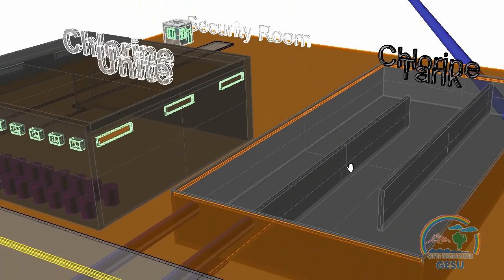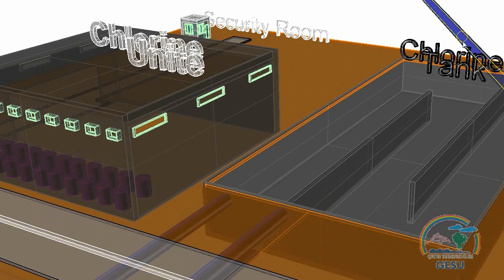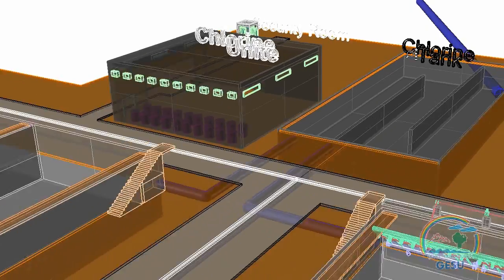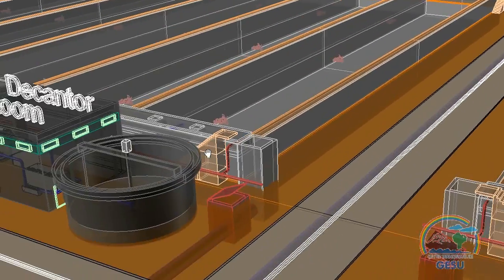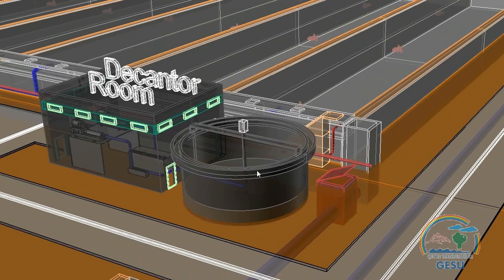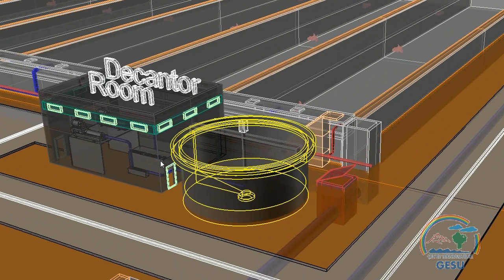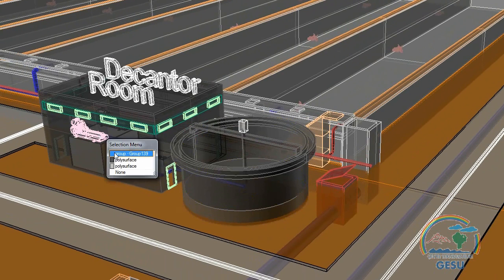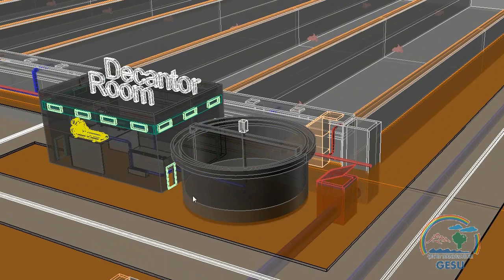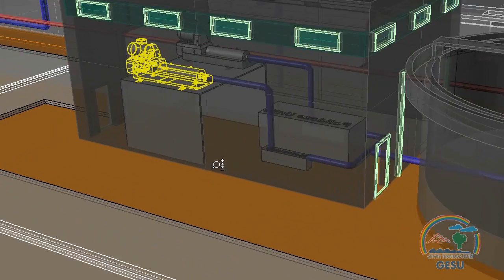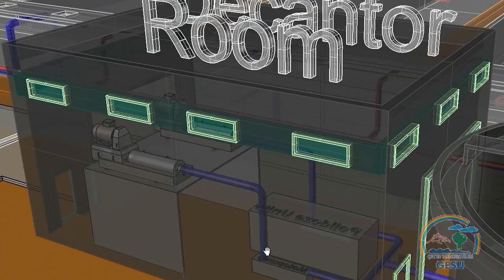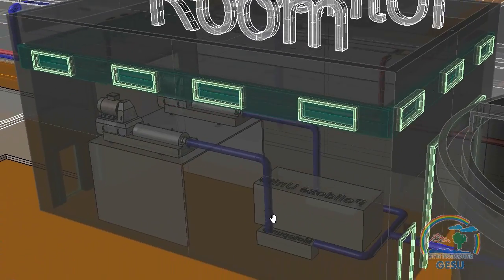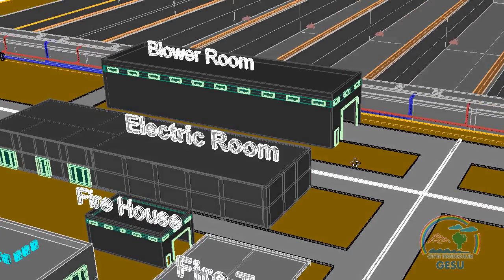Each cycle is 8 hours in total, meaning each tank is filled and decanted 3 times per day. Water is decanted by the discharge structure and goes to the disinfection unit, where gas chlorination is used. Excess sludge from the SBR reactors is thickened by a gravity thickener and then dewatered in a decanter unit.